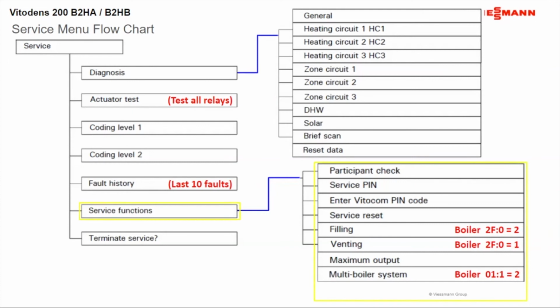Lastly, if you start up the startup wizard and you find that you made a mistake, go into that service function and go down to the very bottom. It says reset the wizard. As soon as you click OK on that, it's right back to set English. It's that quick. So if you made a mistake on your heating curves and you don't want to go back through settings and find heating curves, you can go right here and do reset the wizard and start right from the beginning again.